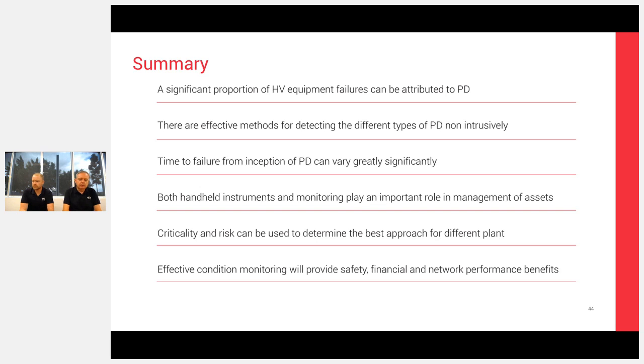So what we can do, because it's a relatively simple case to reposition due to the magnetic nature, we usually put one on an appropriate part of the switchgear, depending on the type. So we make an assessment of the type of the switchgear, the construction. Sometimes we'll put two sensors, but generally it's one or one every other, and we'll see where signals will go. So that's how we'll make an assessment on the TEV, because it will transfer.